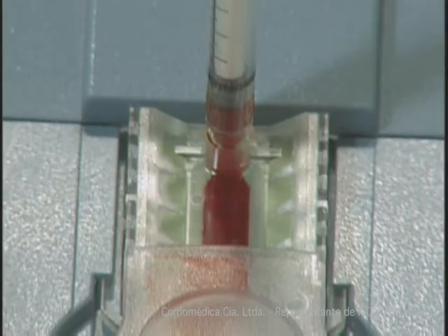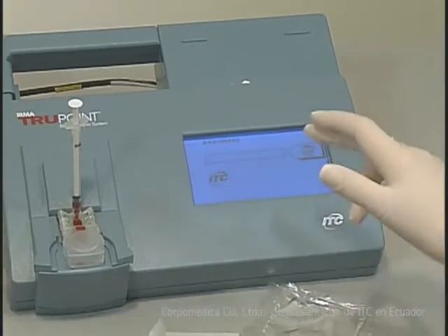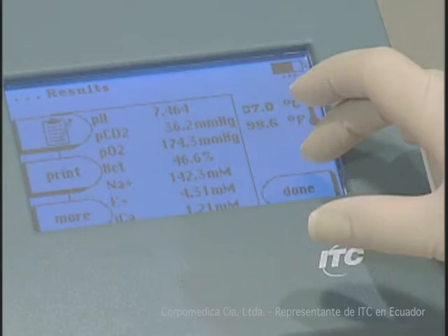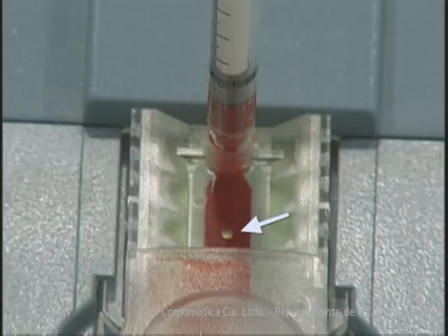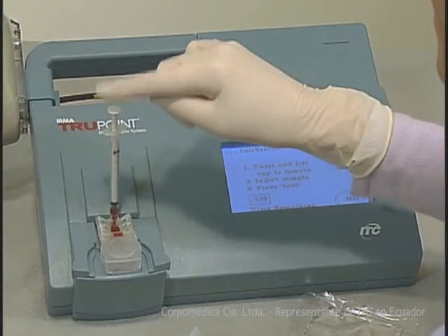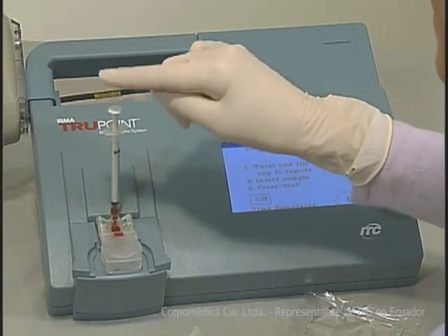Notice the barrel has not reached the bottom of the syringe, because doing so may cause hemolysis and artificially raise potassium. Make sure that the sensor path and all sensors are completely covered prior to pressing Test. If sensors and path are covered, press Test. Review the results and press Done. In the event that gel debris or bubbles are present prior to pressing Test, lightly tap the syringe plunger to cover the sensors with blood.